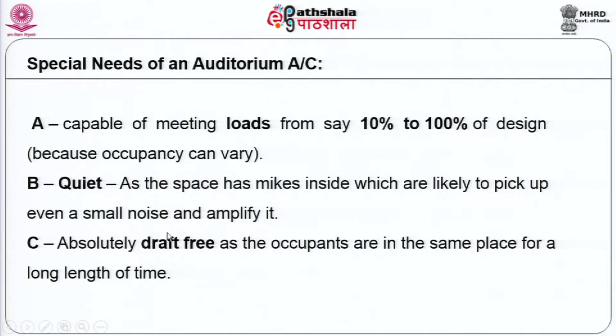What does this different load pattern impose on the designer? The basic item is that when you design an auditorium, you might say that it will be designed for 1000 people. But the 1000 people will be perhaps present only for a peak performance. It is not unlikely that you will have a very small crowd in quite a few instances. So, the air conditioning equipment will have to be designed to be able to meet a very small load and yet cater to the large load. So, the equipment has to be engineered to meet a varying load.